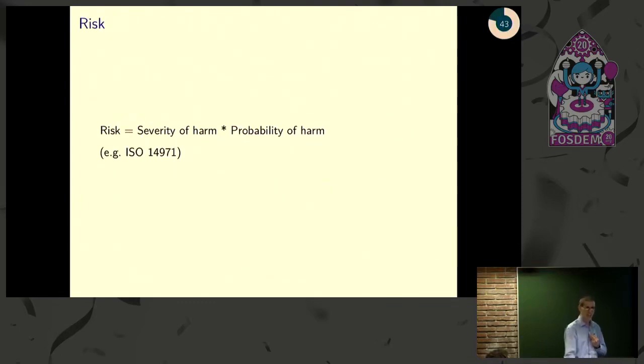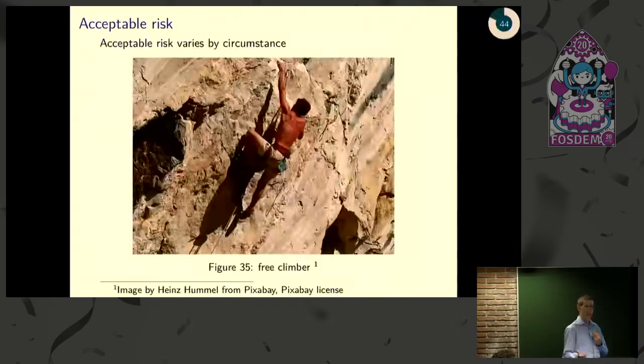Once you have that amount of harm and likelihood of harm, you can calculate or approximate a risk. There are formal design methodologies you can go through for this, but the main idea is you just combine the two and come up with, in your mind, is this an acceptable level of risk? And what's acceptable can vary quite a bit.